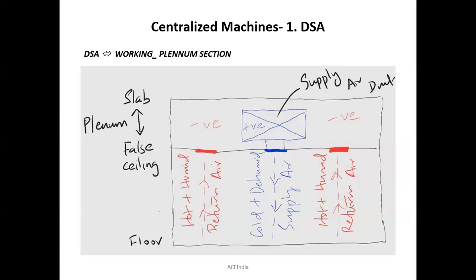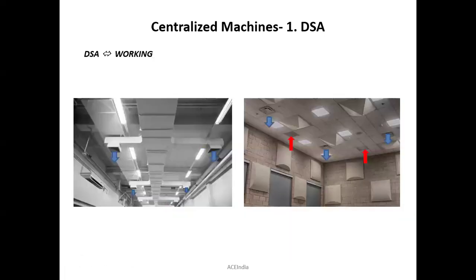So this is the thing, guys. I told you now, the duct should be termed the supply side, which means the positive side, and the other connections, especially the return side, act as the negative side. You can see this now. First of all, in each and every room you will have both supply terminals and return terminals. That is mandatory. Just remember, guys, the return air area should always be greater than the supply air area. We can discuss these parameters later in the duct designing topic.